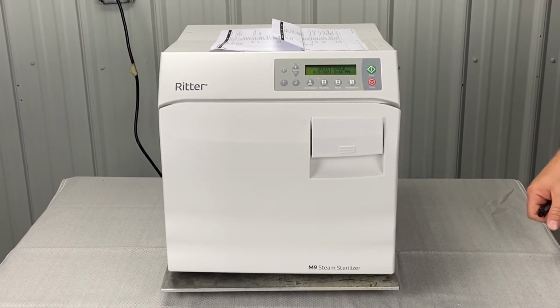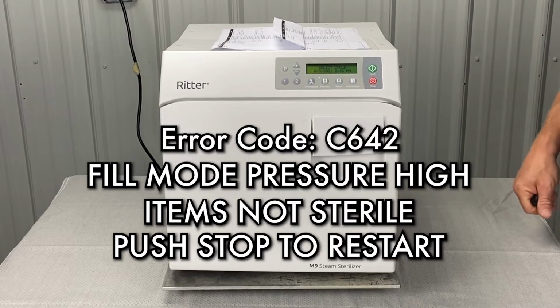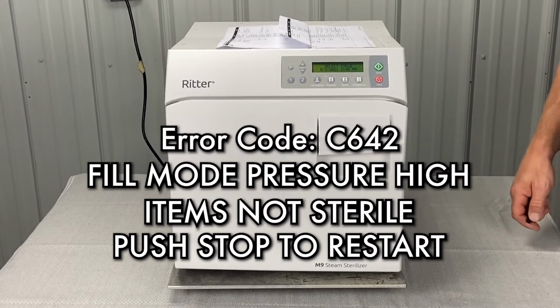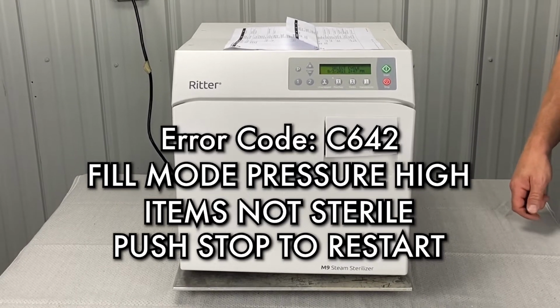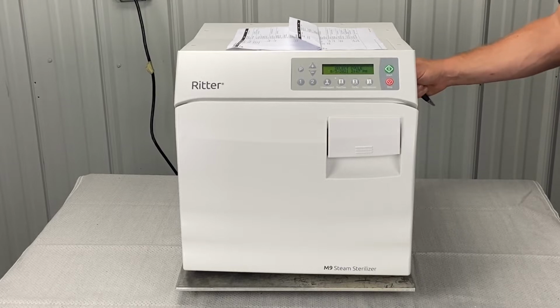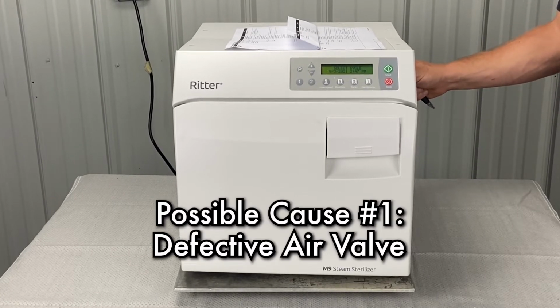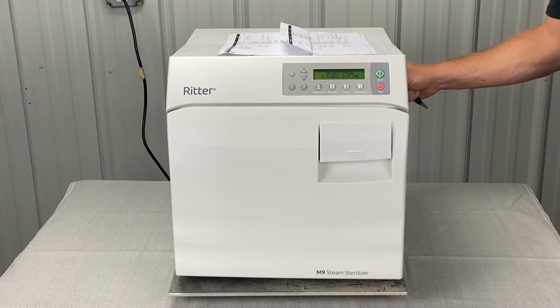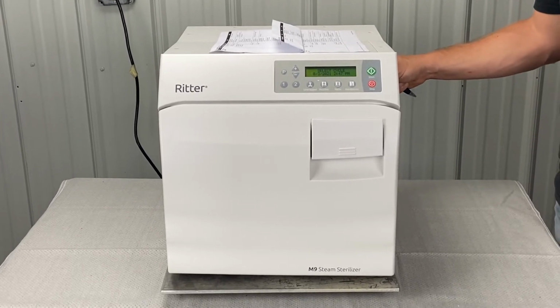Right now we're going to talk about Charlie 642 error code. Charlie 642, fill mode, pressure too high, items not sterile, push stop to restart. First thing it talks about is a defective air valve. We have leaking or defective air valve. Perform air valve test. Check for excessive steam coming through condensing coil spout.